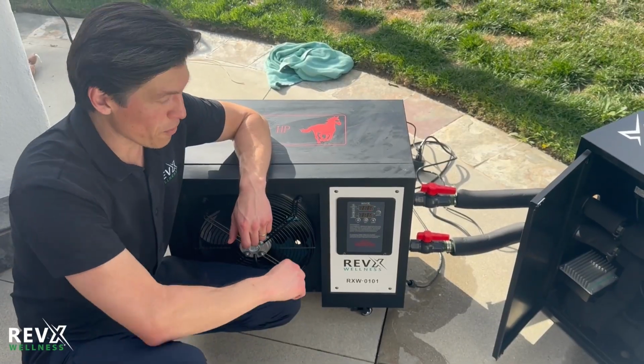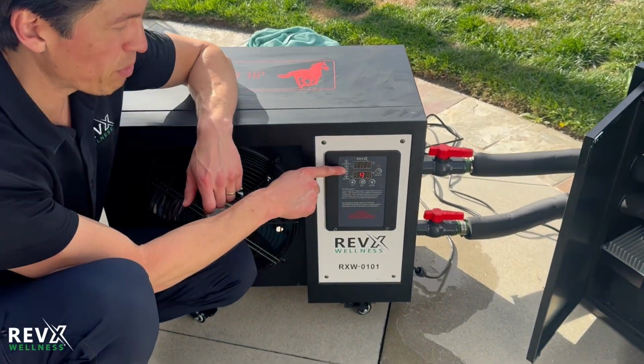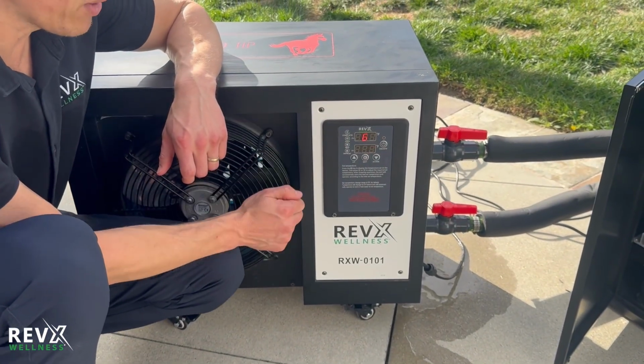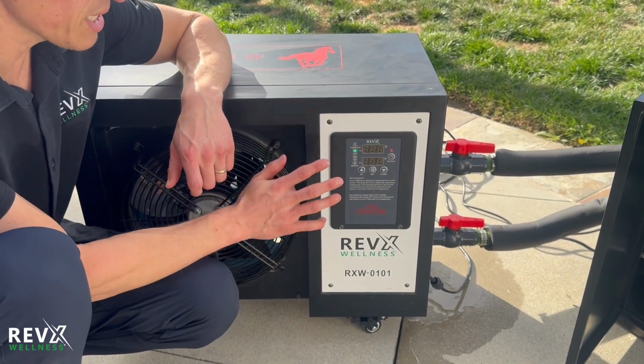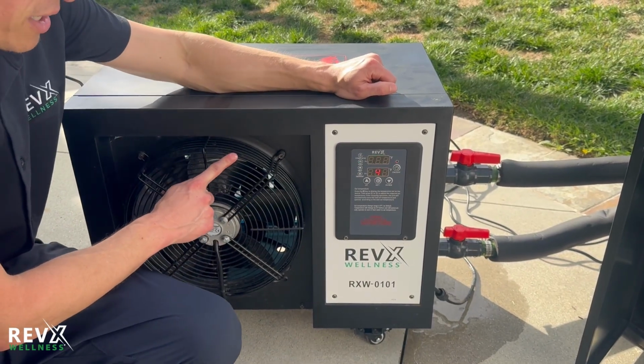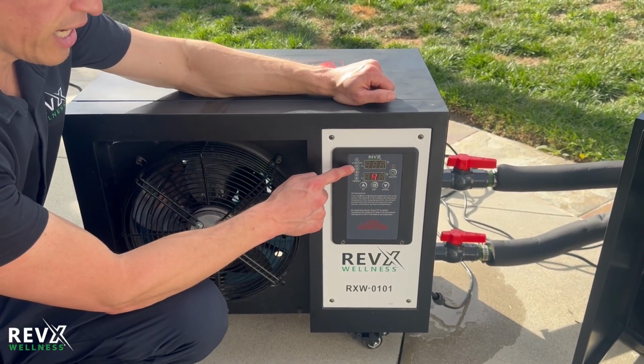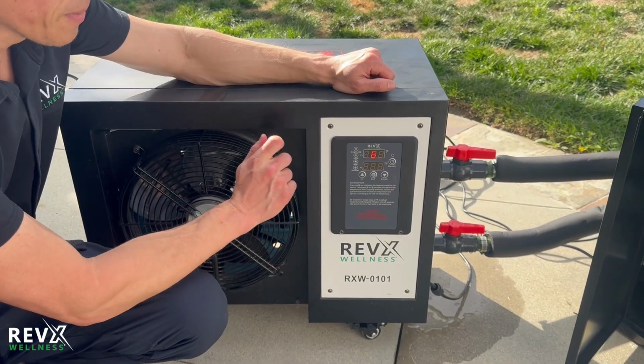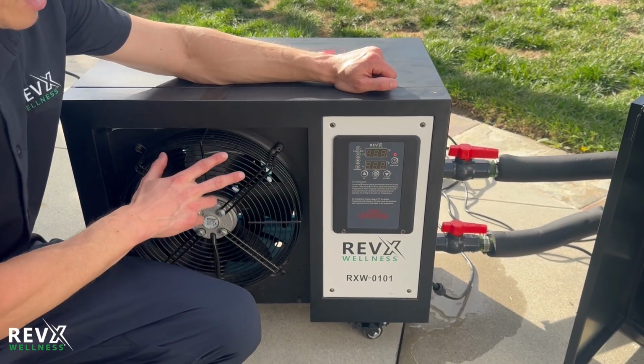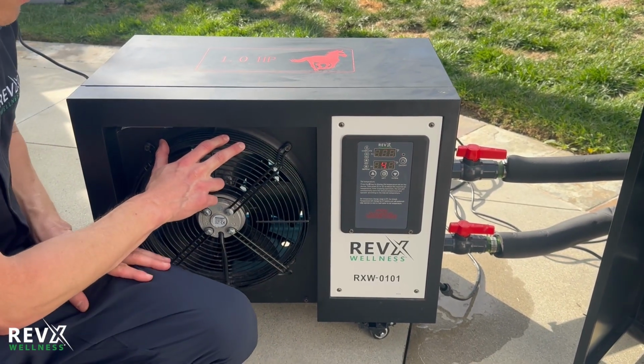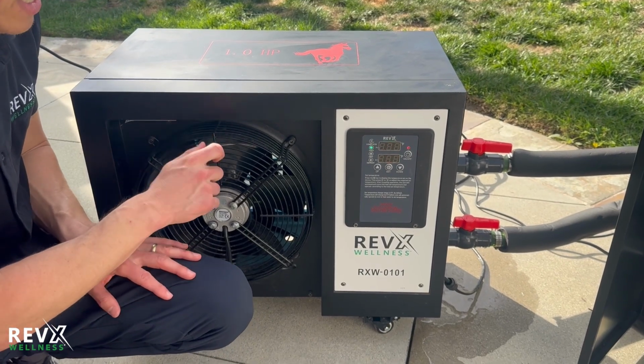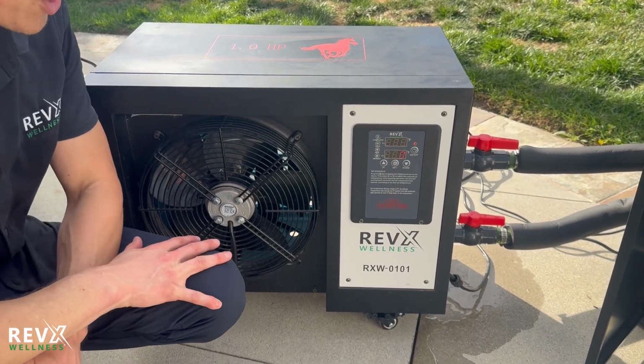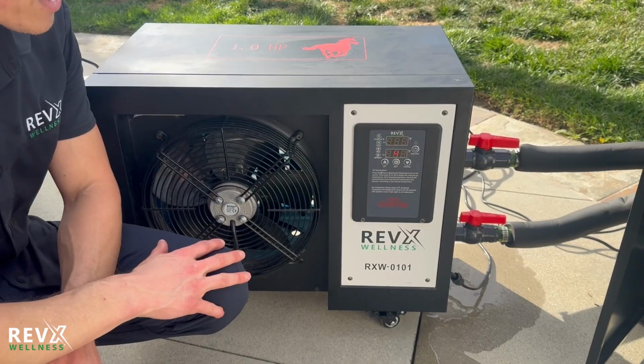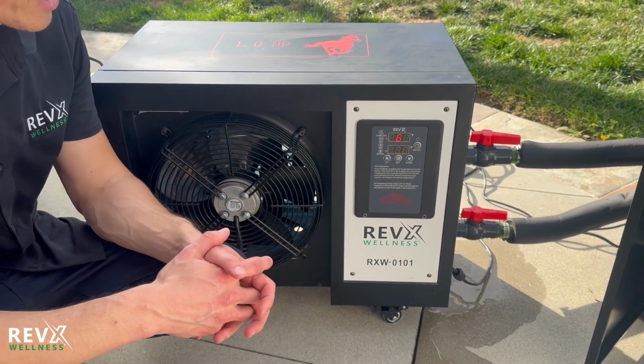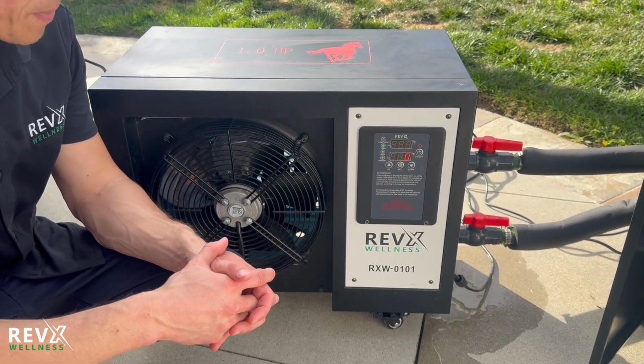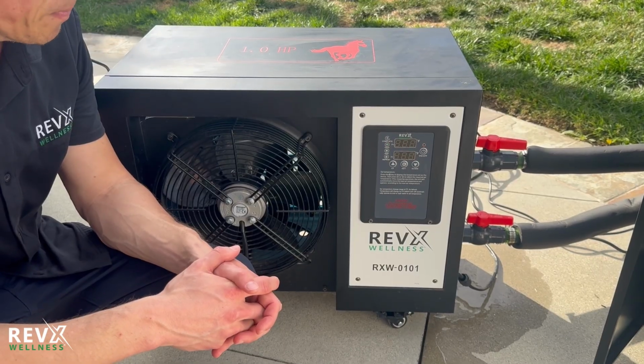All right, so the cooling light's been blinking for a few minutes now. It's about to go into cooling mode. When it does that, the fan will turn on and this cold light will become solid and not blinking. And in about 10 seconds after that, you will hear the compressor click in. And that is how loud our chillers are. It's about 50 dB or so. It sounds just like a loud floor fan in your house. So let's wait for that to happen.